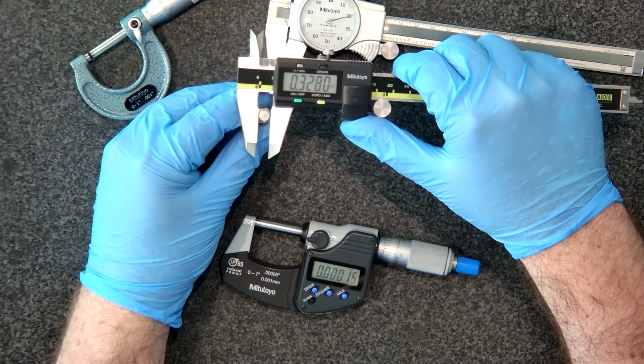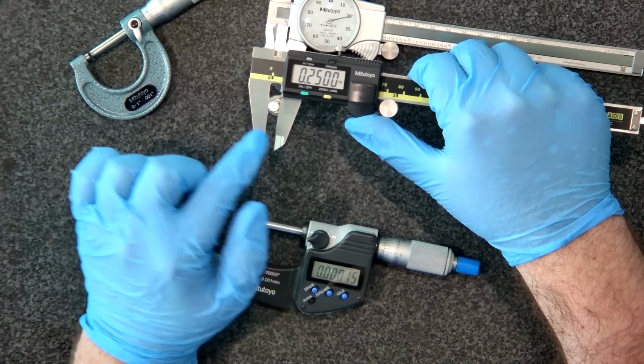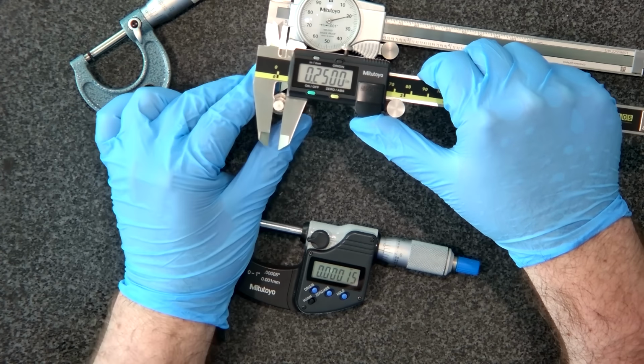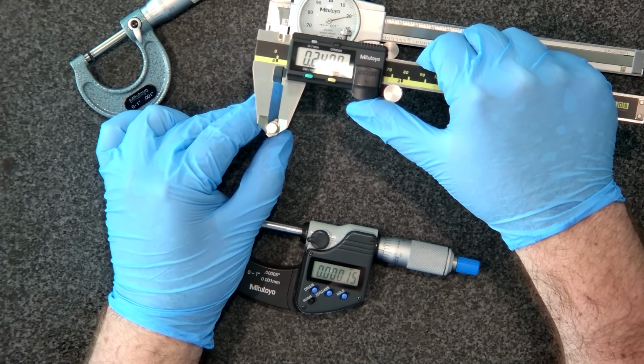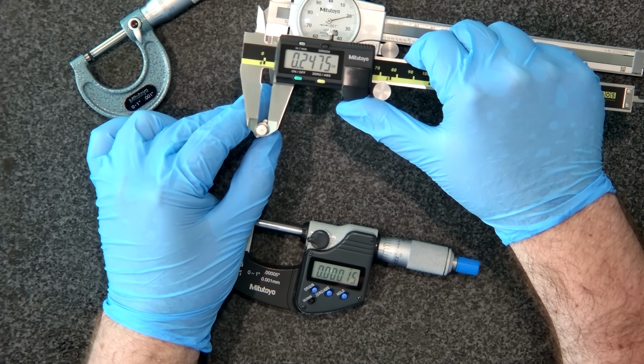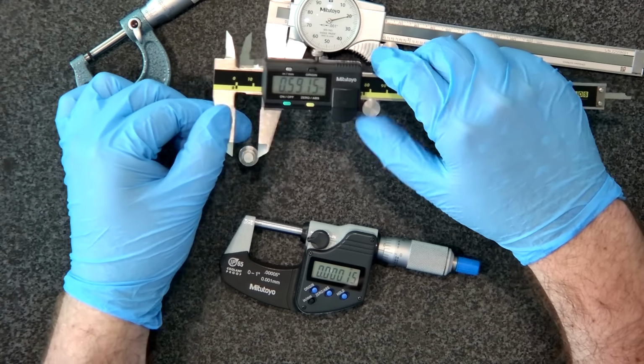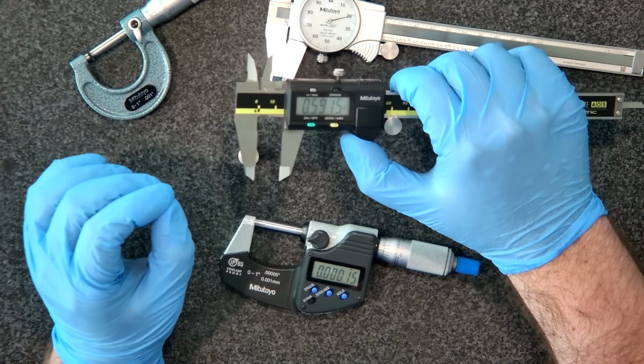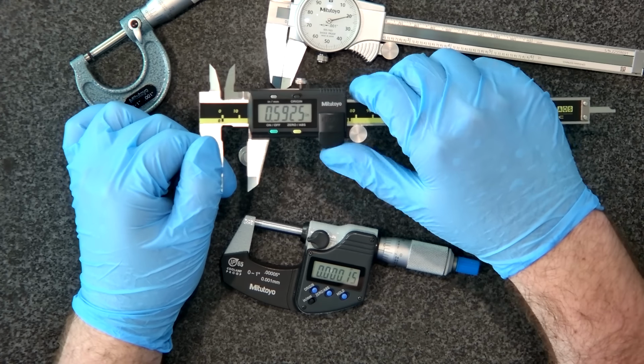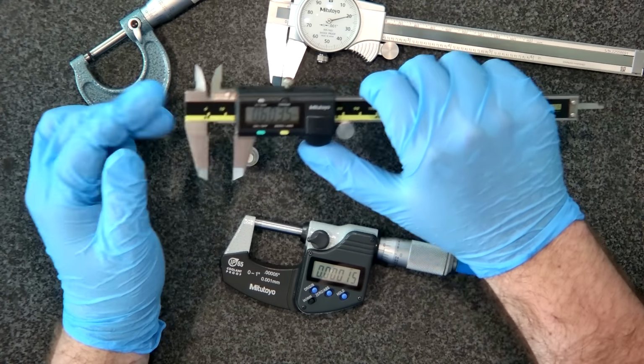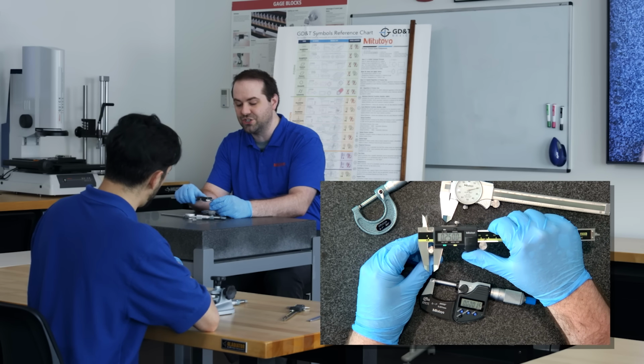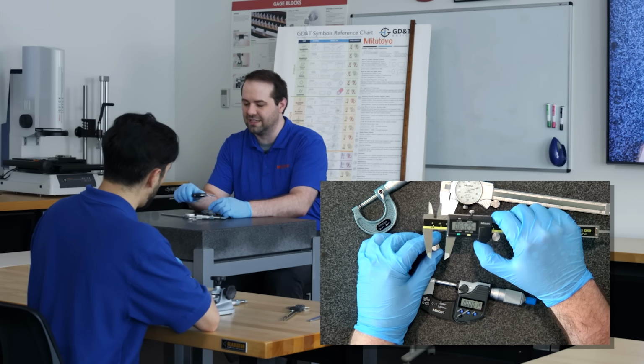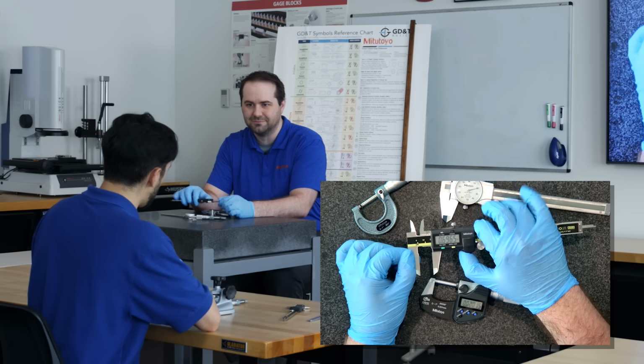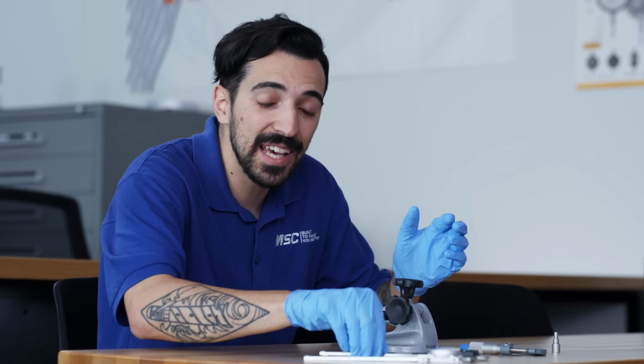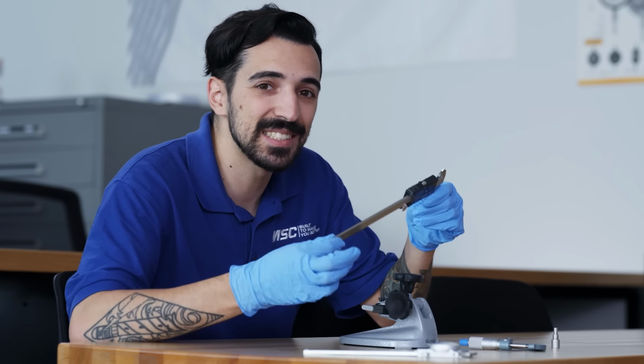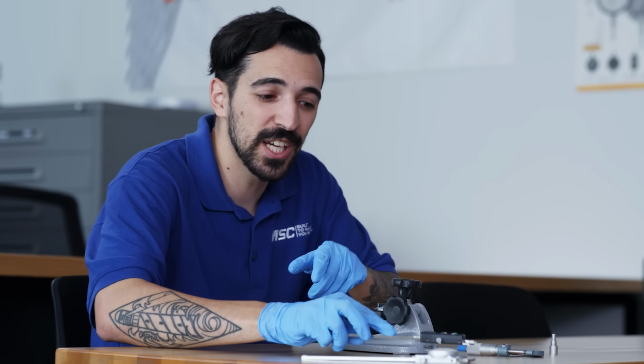So if I'm measuring at the top of the jaws, I can start putting too much pressure on my thumb and not really affect that measurement too much. But if I go down to the bottom of the jaws and I start squeezing, I can affect that number very, very quickly. Yeah. So the technique in your finger placement, the consistency in that is critically important. If your thumb's dancing around or you're handling this thing in all sorts of weird different ways, your ability to feel that pressure is not going to be good. It's not going to work very well if you're using inconsistent technique. This just goes to show, even if you have a high-end piece of equipment, if you're not using it consistently, it's not going to be reliable. Let's go check in with Jeff to learn a little more.